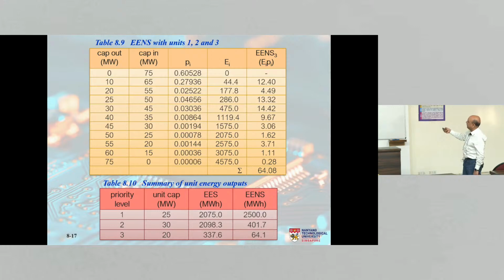So capacity is 75 all the way up to 0, and EI for 75 is 0 because it is just meeting the load demand. And then in all the other cases there is some energy that is not supplied, and the energy not supplied at the end is only 64 megawatt hours for that 100-hour load duration curve. Okay. So this is the summary of the unit energy generated. The first generator is generating 2000 megawatt hours, the second generator is generating a similar amount, the third generator is generating only 337 megawatt hours. And the total risk in the system is 64.1 megawatt hours per period. Okay. Two examples to illustrate how we calculate the risk and how we calculate the energy supplied by each generator.